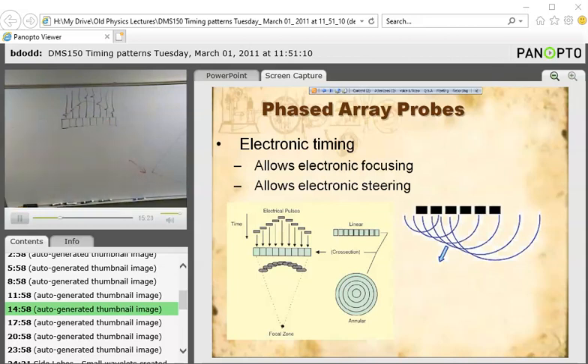So now we've got a wavefront, you can see, is concave. And it's going to travel in this concave fashion into a point, right? So what's going to happen is instead of focusing, now you would expect a big wide crystal diameter like that to focus very deep, right? Ivy, that's what we had before. We had a wide crystal, you said, and it's going to focus deep. But if we change this wave pattern so that it's curved, what's going to happen is it's going to come in and focus very shallow. Okay? Just like that. This curved pattern is going to cause the focusing to be very shallow, even though it's a wide crystal diameter.